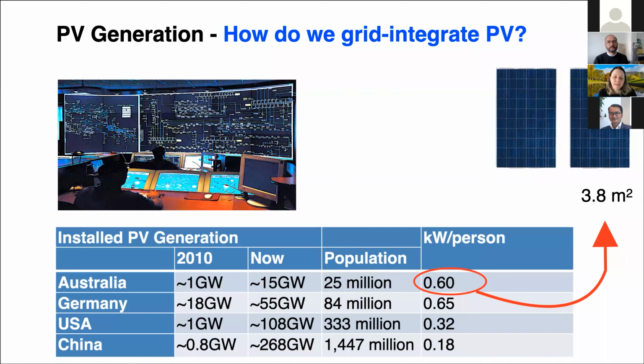integrating the solar resource. Traditionally, distribution grids were designed for one-way power flow from the generator to the customer, with operators monitoring and remotely controlling the grid. Actuation has been limited to opening and closing switches, tap changing transformers, and switching in capacitors. And as a last resort, switching off the load.